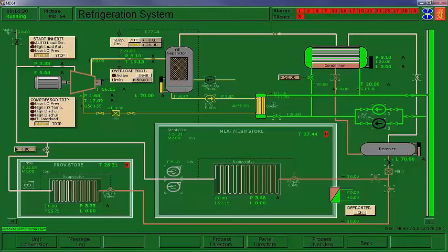Now, what I'm doing initially, that's 3 bar suction pressure. Now, that's 45 pounds. I would be worried about any liquids that had formed in this system while it was shut down and the possibility of liquid slugging back. So in the beginning, I'm not going to put any liquid on. I'm going to wait till this drops down to about one bar, and then I'll go ahead and put the system in automatic.